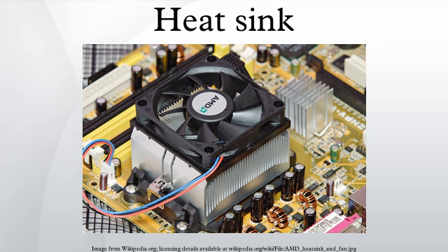The above equations show that, when the airflow through the heat sink decreases, this results in an increase in the average air temperature. This in turn increases the heat sink base temperature. And additionally, the thermal resistance of the heat sink will also increase. The net result is a higher heat sink base temperature. The increase in heat sink thermal resistance with decrease in flow rate will be shown later in this article.